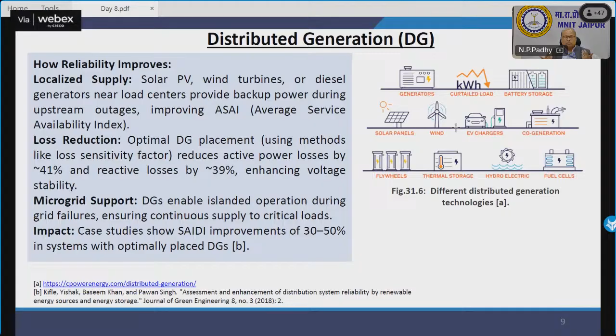Good. So then what about the energy storage system? This is also very common. We understood the basics. If you have a PV-based grid supply system and you have a battery, then you can charge your battery and supply the rest to the grid. And as and when the load requires, you can discharge from the battery. So first of all, there is backup power. Battery supplies critical load during outages, bridging gaps until grid or DG power resumes. Peak savings: ESS reduces feeder congestion during high demand, preventing overload-induced failures.